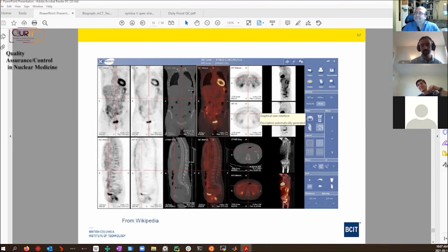Something that happened recently in our clinic is one day our dose calibrators started shifting. We saw it shifting, and then we did the measurement the next day, and it was shifting a little bit more than the day before. So I immediately noticed, okay, this is a trend. It's showing us that this equipment is actually starting to fail. So then you go and talk to management in the clinic and say, we need to buy a new dose calibrator. And they say, why? And I say, well, because it's failing. And how do you know it's failing? So then you show this data, and they see the trend, and we're not going to be able to use it in 2 weeks if we continue at this rate. So there's all this data proving this, and of course, then you immediately get the budget to buy the new dose calibrator.